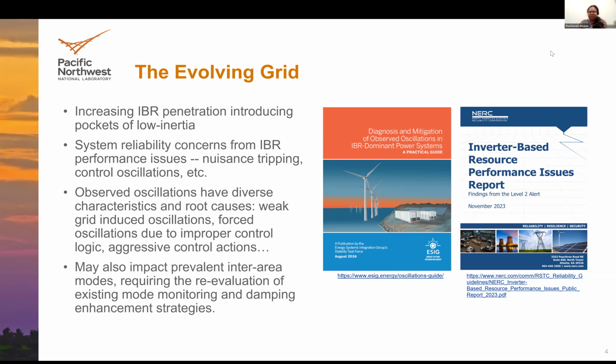I'm going to talk a little bit about the oscillations and the different types of oscillations that the IBRs are introducing in the system. I'm specifically going to talk about the phasor measurement unit data. I'm sure, again, you are aware, but phasor measurement units basically provide high resolution, time synchronized snapshots of electrical phasor quantities, and they help in providing a diagnostic tool of what is happening in the grid at the fundamental frequency, and basically give a much better understanding of the dynamics compared to SCADA.